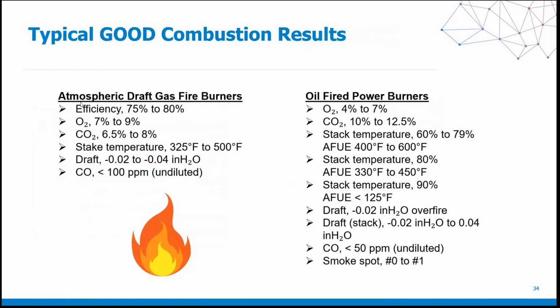Some different combustion results that we consider to be on the good side of the equation. We have a couple of different systems here. For an atmospheric system, we look at an oxygen percentage of 7 to 9%, CO2 of 6.5 up to 8, and we have CO under 100 ppm. And that is a general guideline in our industry. The under 100 ppm in the stack is what you should always be striving for.